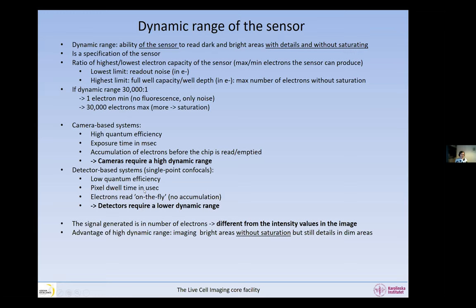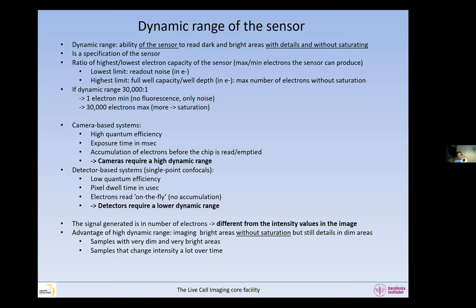The advantage of a sensor with a high dynamic range is that you can image bright areas without saturating while still getting detail in dim areas. Samples that require a high dynamic range are those with very dim and very bright areas, or samples that change intensity a lot over time — for example, tracking protein expression over time. The disadvantage is that imaging is slower.